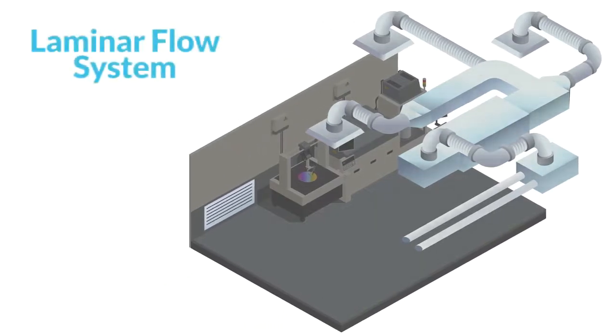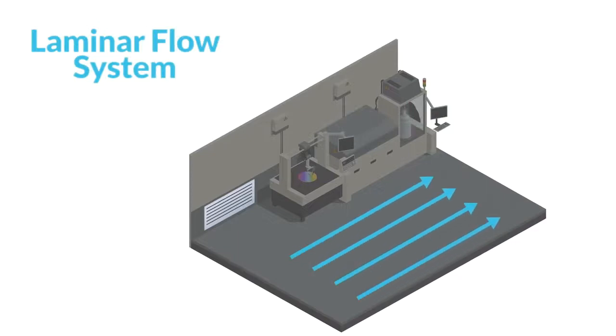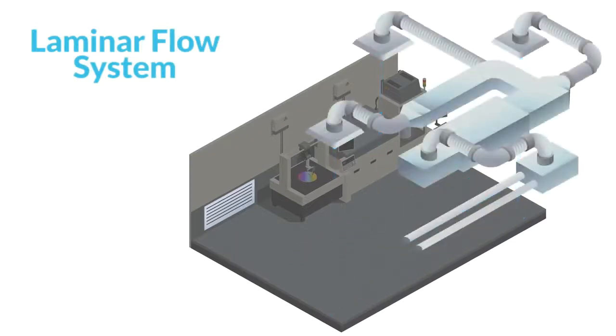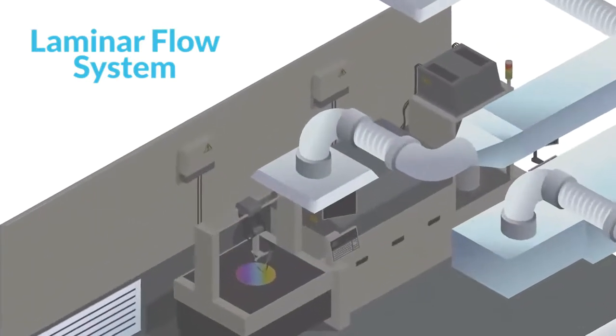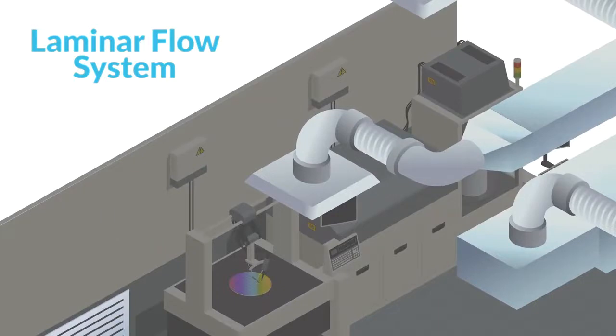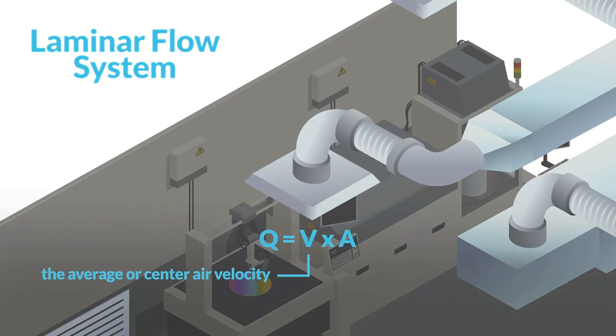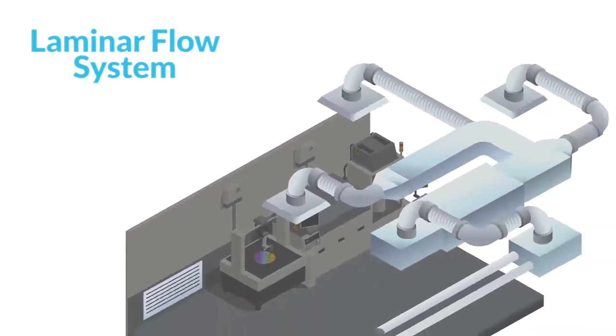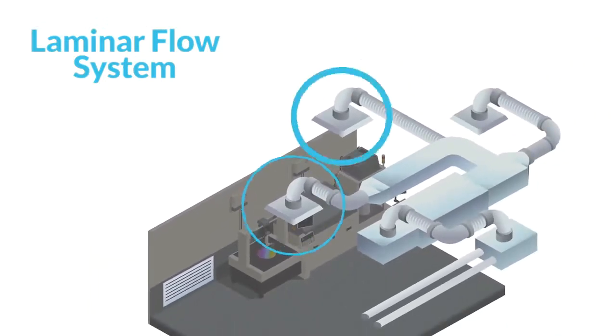The first is called a laminar flow system. In this setup, air flows through the clean room in one direction, either horizontally or top to bottom. To confirm that the system is working properly, check the airspeed at the supply vents as well as the distribution of air velocity throughout the room. You can also measure the volumetric flow at the supply vents or fan filters by using the following formula: Q equals V times A, where V is the average or center air velocity and A is the area of the vent or fan filter. And to measure the room's total volumetric flow, you perform the same measurements at each of the supply vents or fan filters and sum the results.